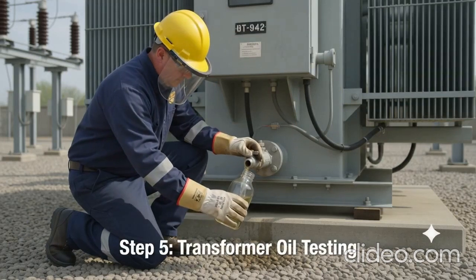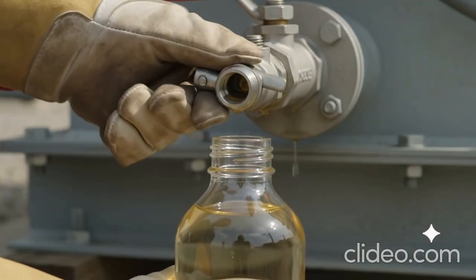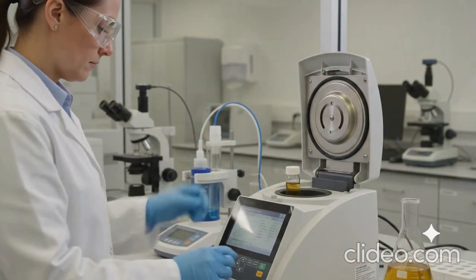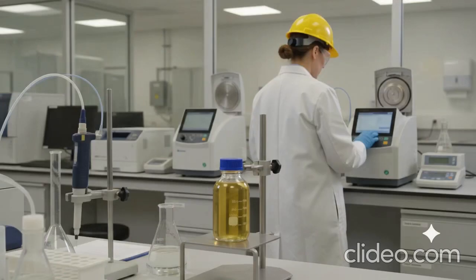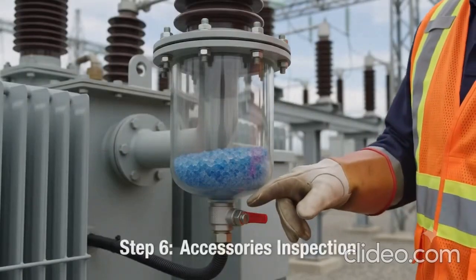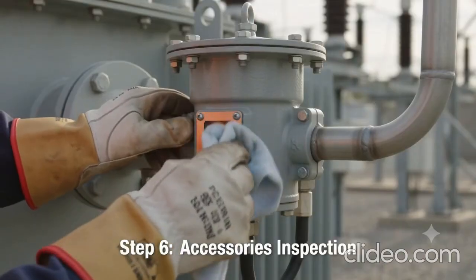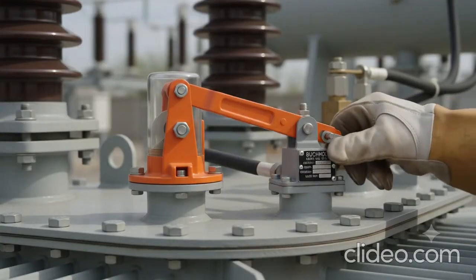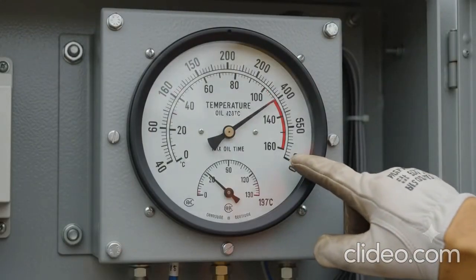Transformer oil is inspected. A representative oil sample is collected for laboratory testing. Tests include dielectric strength and dissolved gas analysis. Transformer accessories are also inspected. The breather, silica gel, Buchholz relay, and oil level indicators are checked.